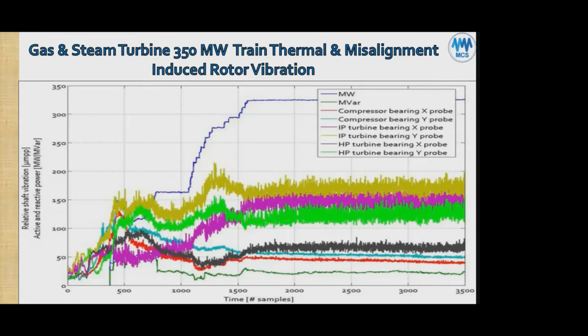the bearings. The bearings were growing thermally in unusual ways, the bearing housings and the bearing itself. They were also having a thermal stress transient vibration inside the rotor of the IP turbine, mostly. As you can see, the bad actor here is mostly the IP turbine, with the purple and the tan, and below that we have more reasonable numbers. For example, we have the HP turbine bearing. You see the black line. The HP turbine is running at something like 60 microns maximum, which is nice and smooth. It's great. So we're mostly talking about the top three.